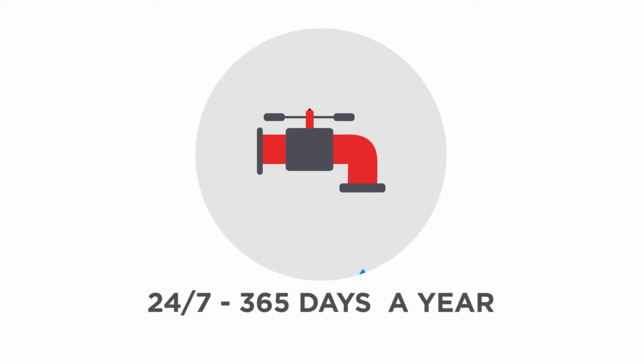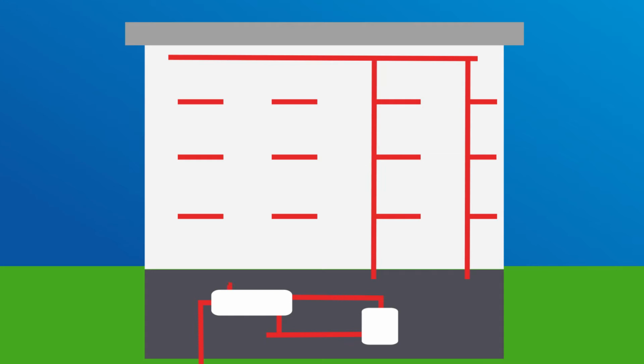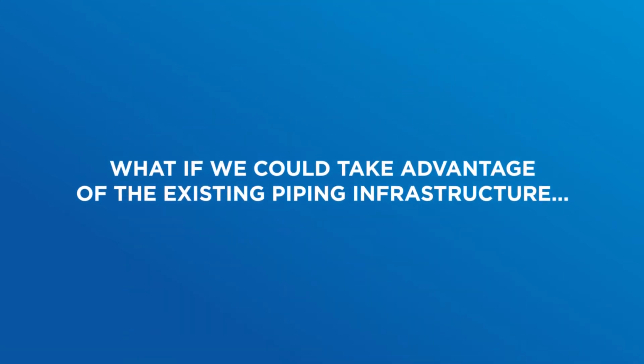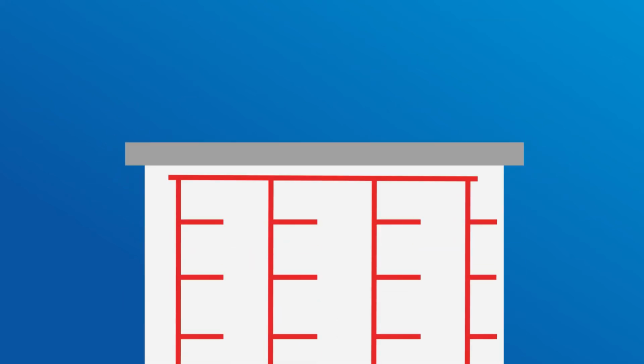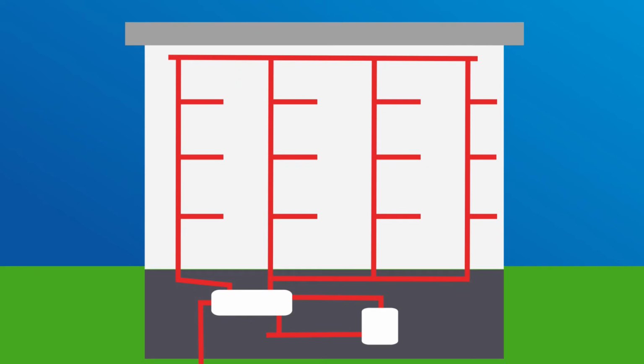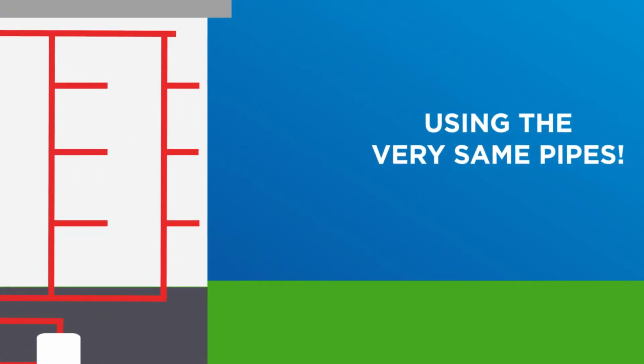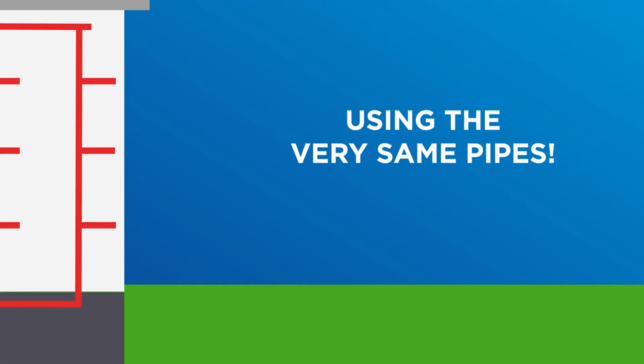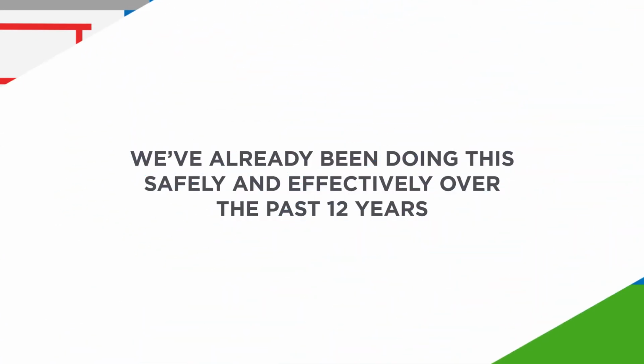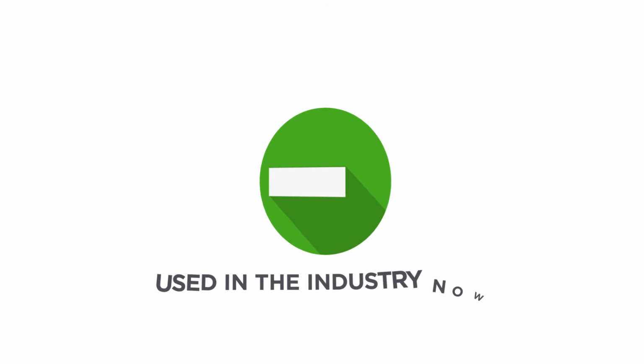This means they have to have domestic hot and cold water piping in the buildings running to each occupied tenant space. What if we could take advantage of that existing piping infrastructure and the domestic hot and cold water already in the building to satisfy the heating and cooling requirements using the very same pipes? Well, not only can we do that, but we've already been doing this safely and effectively over the past 12 years. In order to understand the impact that IPS makes, we need to explore the advantages and disadvantages of the systems being used in the industry now.